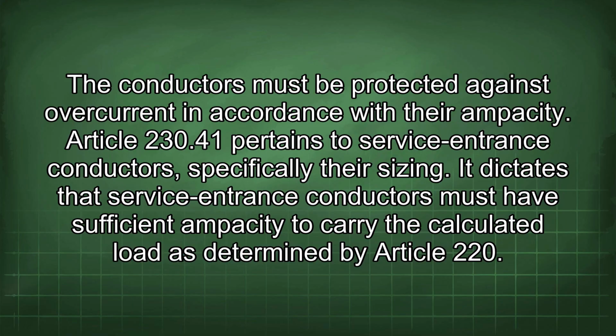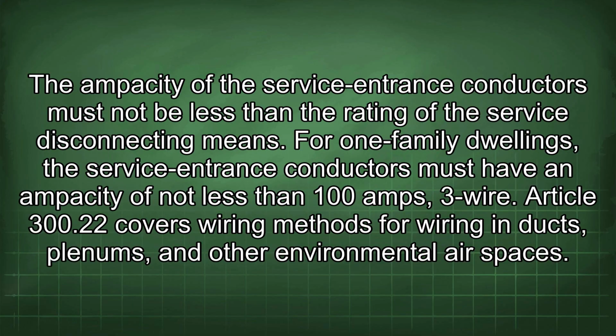Article 230.41 pertains to service entrance conductors, specifically their sizing. It dictates that service entrance conductors must have sufficient ampacity to carry the calculated load as determined by Article 220. The ampacity of the service entrance conductors must not be less than the rating of the service disconnecting means. For one-family dwellings, the service entrance conductors must have an ampacity of not less than 100 amps, 3-wire.